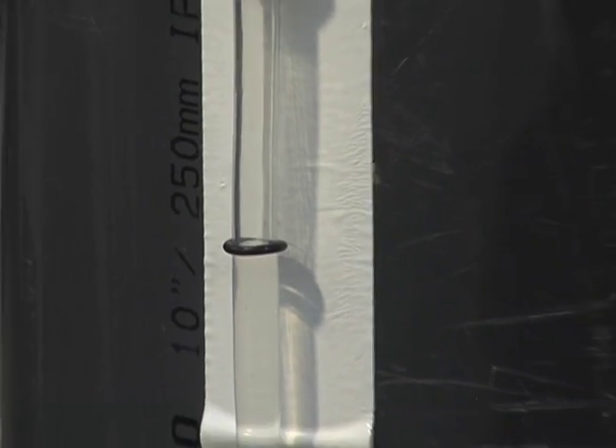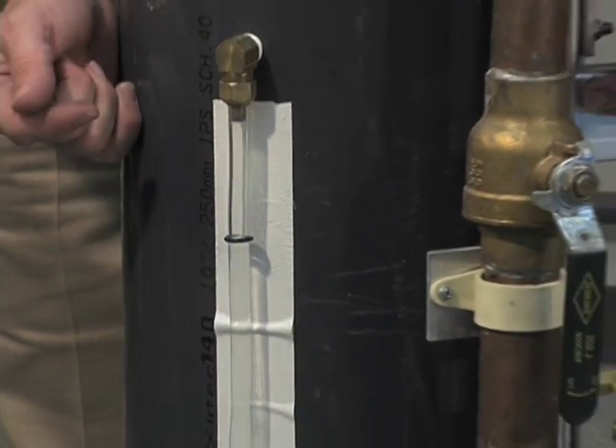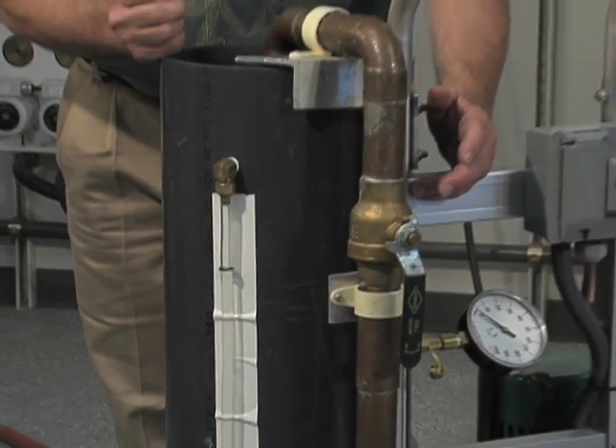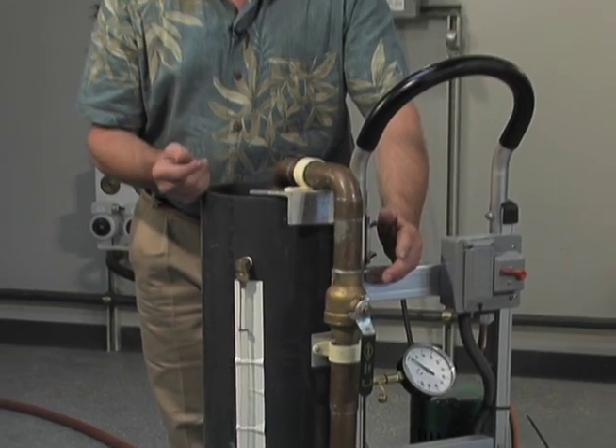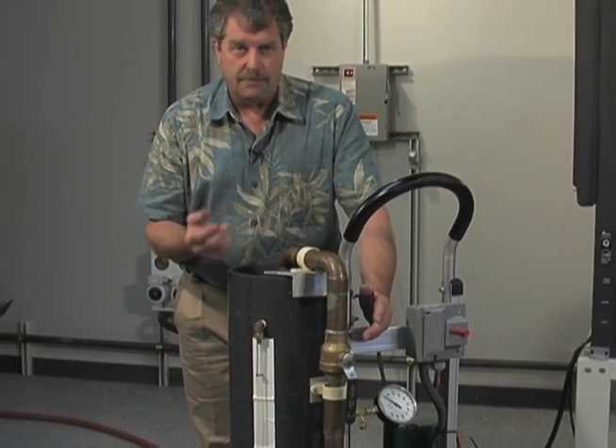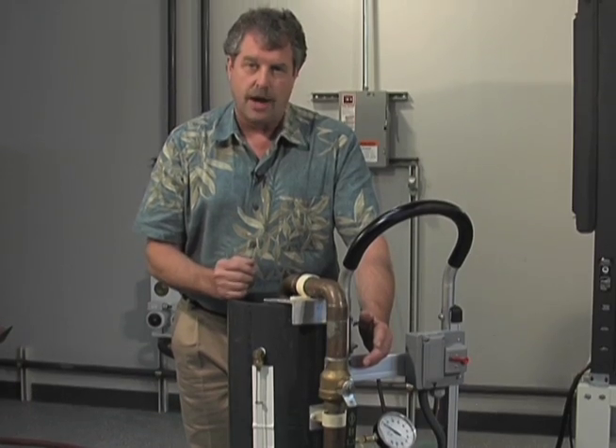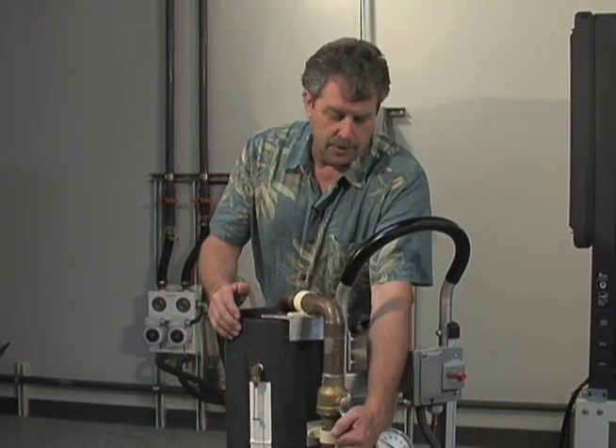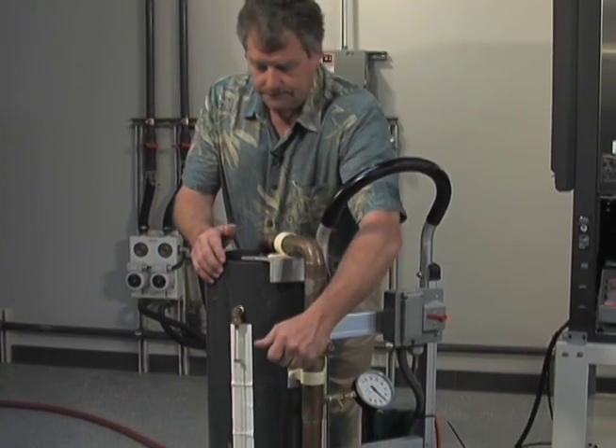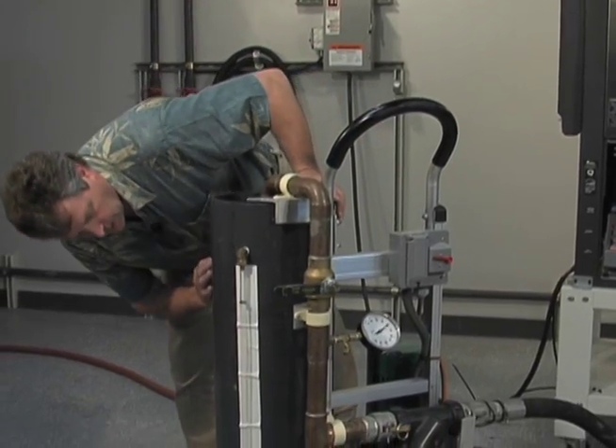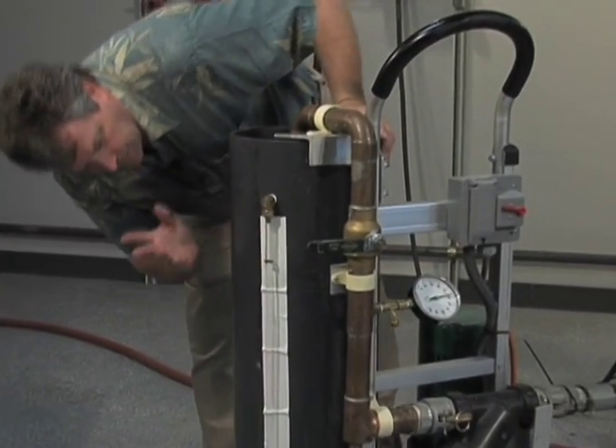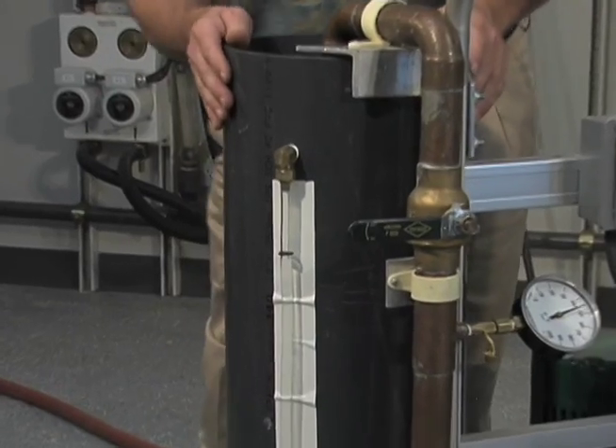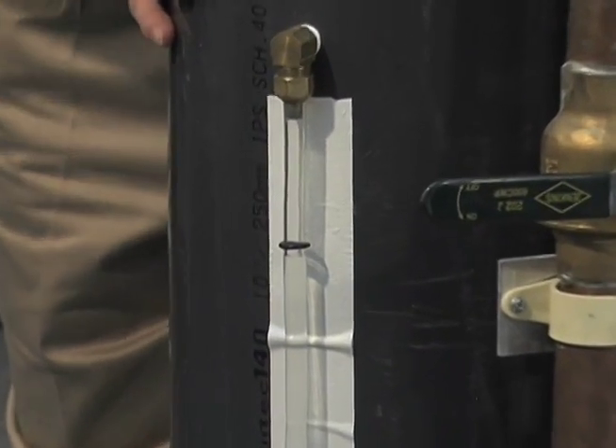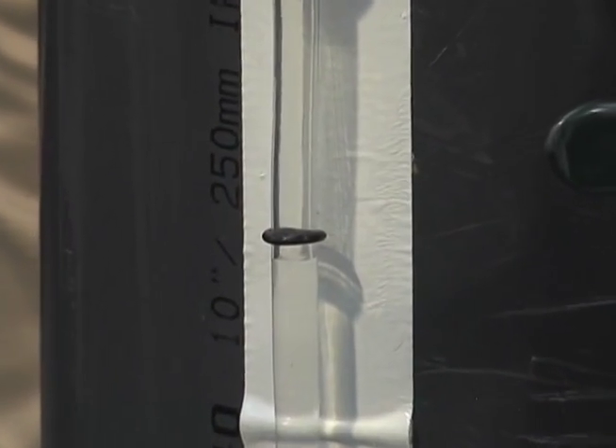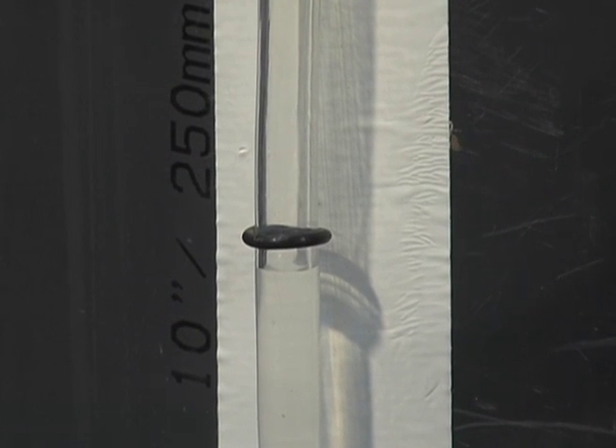And we're going to go ahead and deadhead our system, and we're going to see how much fluid drop we get. Again, in a system like this, we would expect to see no more than about 3/8 of an inch fluid drop. If we get much more than that, that means we still have entrapped air. So let's see how we're doing here. We're going to go ahead and deadhead this. And this one is getting maybe 3/16 of an inch drop, something like that. So I would say that we have successfully moved the air out of the system.